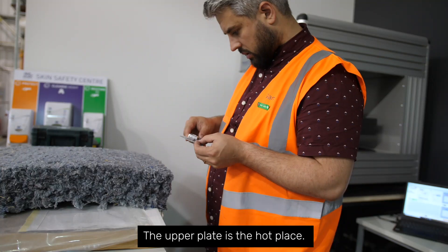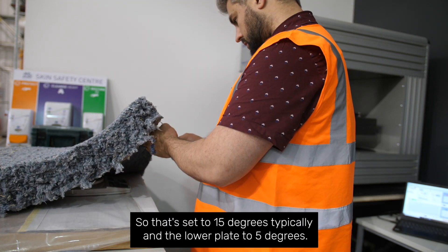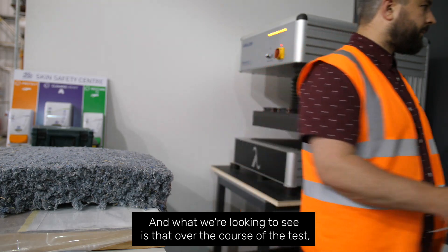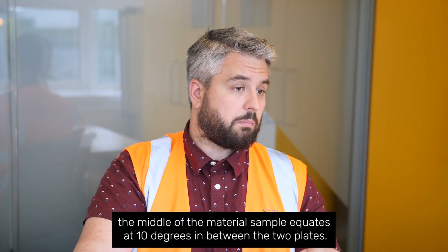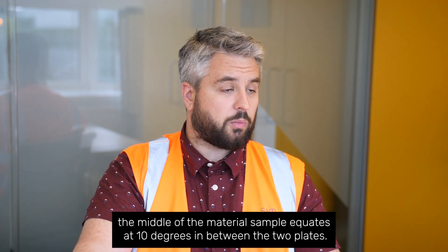The upper plate is the hot plate, set at 15 degrees typically, and the lower plate is set to 5 degrees. What we're looking to see is that over the course of the test the middle of the material sample equates at 10 degrees in between the two plates.